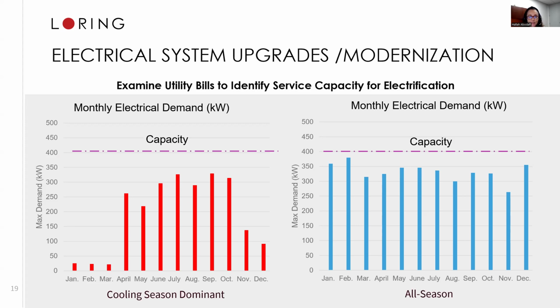You're looking at two charts from buildings we looked at for an electrification solution. The chart on the left is a cooling season dominant building. Yes, they were using a gas boiler in winter to heat their building, but if we offered an electrification solution to the fossil fuels they were burning, these bars would come up to this threshold. It might not reach the purple line where you've got your capacity, so this may be a situation where you don't have to upgrade the electrical capacity.